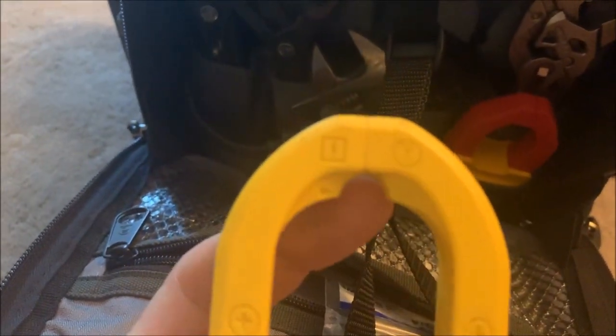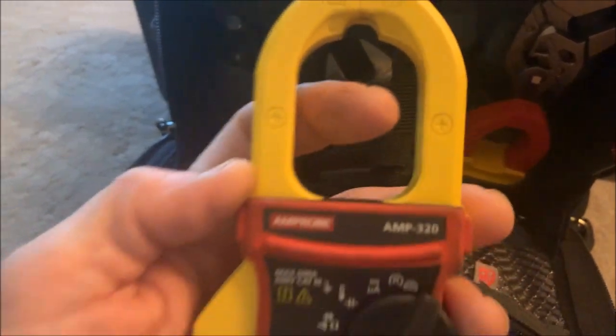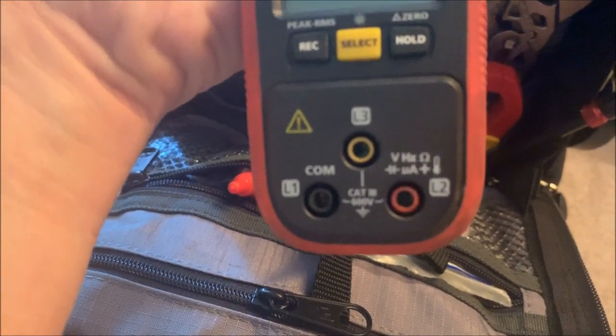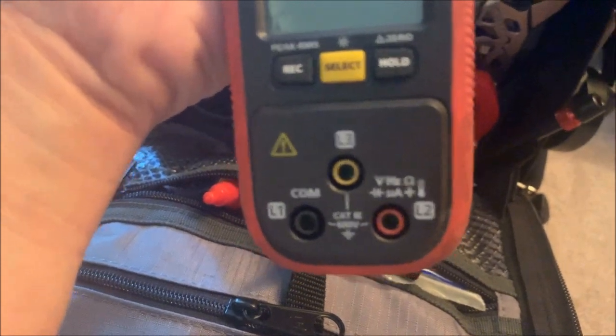I keep it mainly because you can put a wire in here and it will check the amp draw on the wire — anything up to 60 amps — instead of having to clamp around it. That's why I keep this meter; I really like it for that. And three-phase rotation: you can put L1, L2, L3 on here and check the electrical feed coming in and check the rotation on everything.